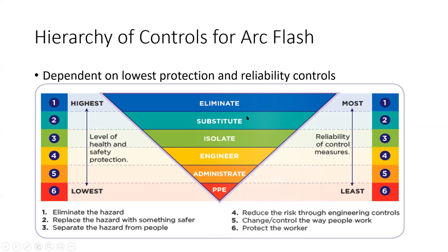So substitution, an example might be to reduce the circuit breaker settings while you're working on the equipment to reduce the incident energy levels. Isolation could be just installing a barrier over the bus bars so that if the spanner or screwdriver was dropped, it's not going to cause an arc flash. And there's many interesting engineering controls coming out all the time. You've probably all seen arc detectors and the arc quenching switchgear that shorts the three phases down to earth and eliminates the arc immediately.